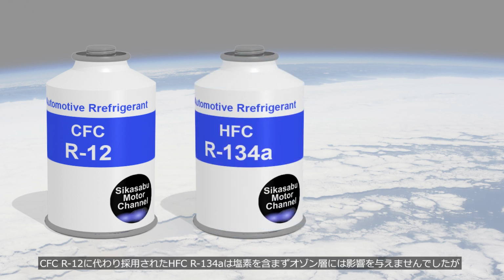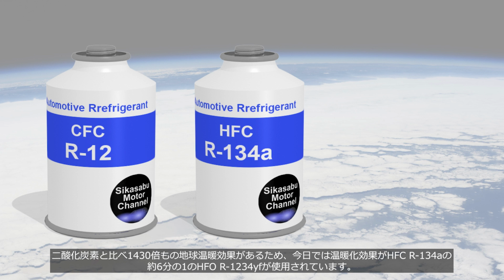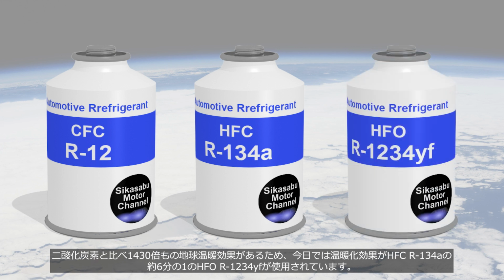HFC R134A, adopted as a replacement for CFC R12, did not contain chlorine and therefore did not impact the ozone layer. However, due to its high global warming potential, approximately 1,430 times that of carbon dioxide, there has been a shift to HFO R1234YF, which has a warming effect about 6 times less than that of HFC R134A.